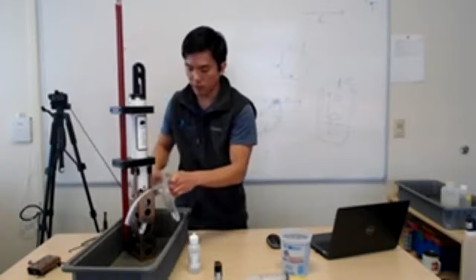This is a brand new HydroCAT, so there's nothing coming out. If you want to clean your instrument, what you can do is take some 1% surfactant solution. So this can be Triton X, Tergitol, basically a scientific grade detergent is what you want to use. 1% detergent, 99% deionized water. And then do pretty much the same procedure where we're filling up our syringe with our cleaning solution. And then we're installing the hose barbs, the tubing here. And we're doing the same thing.